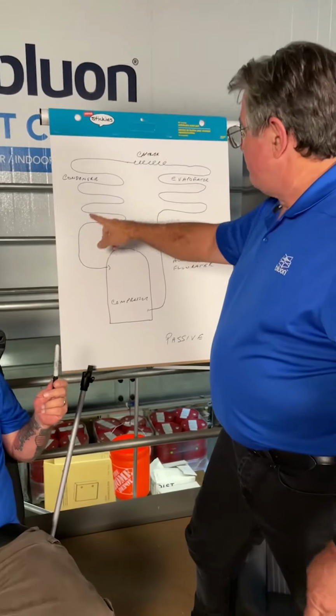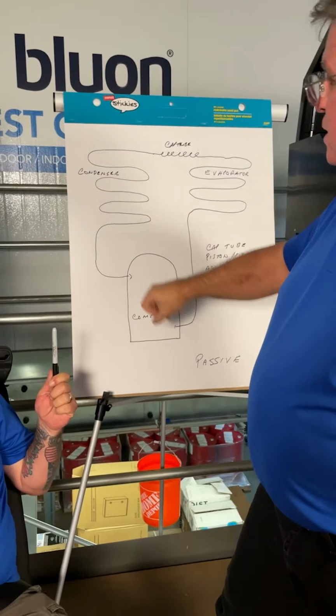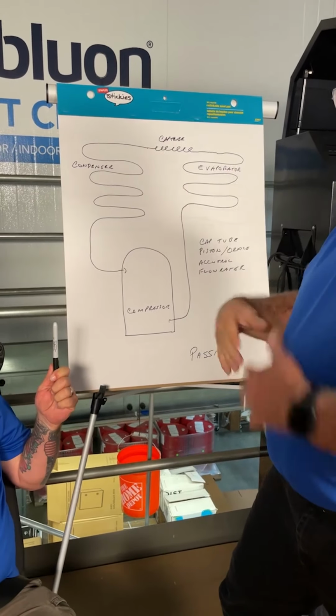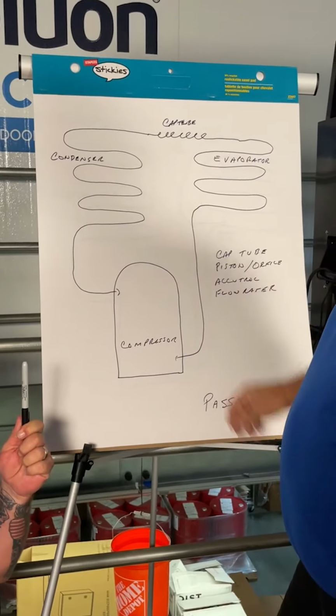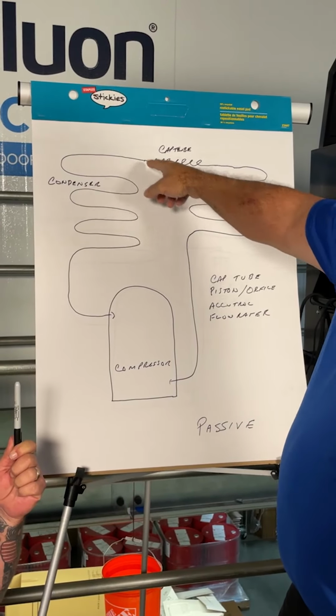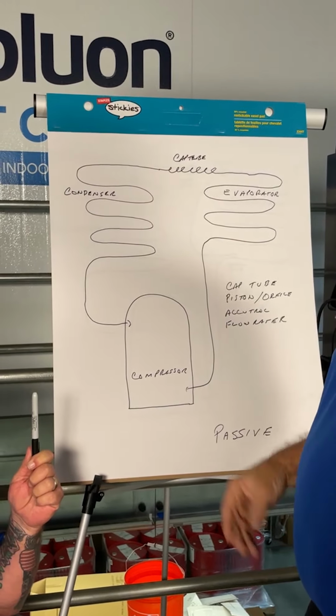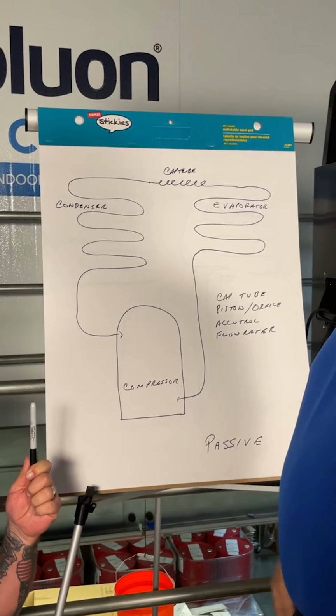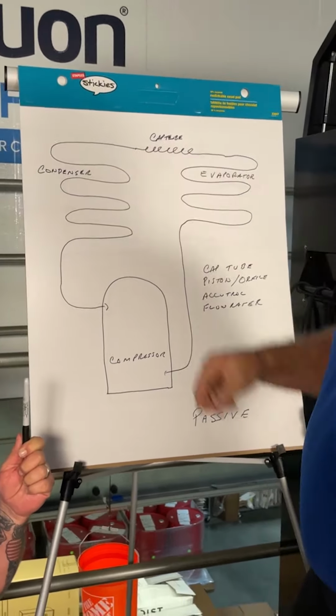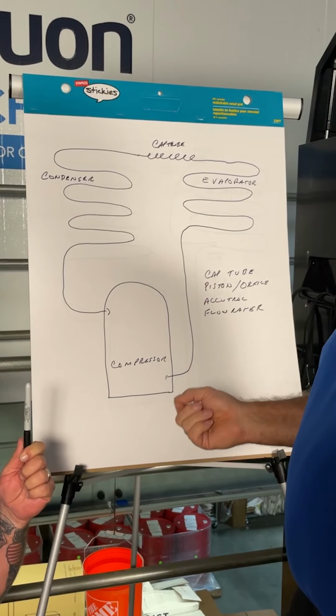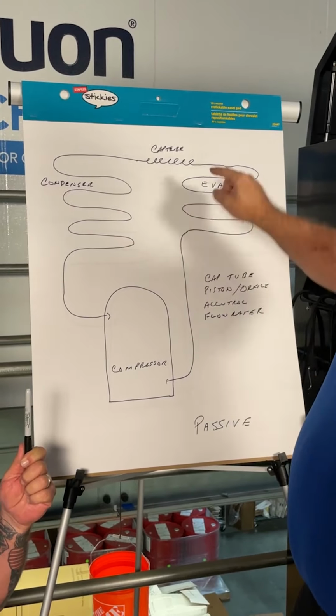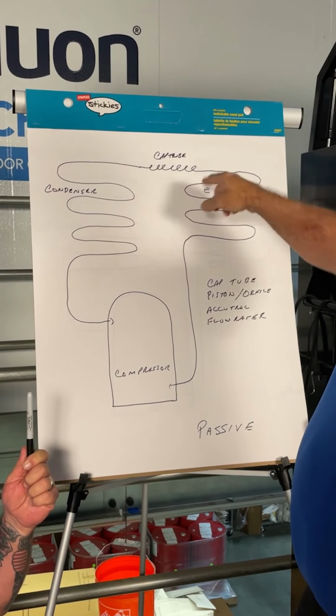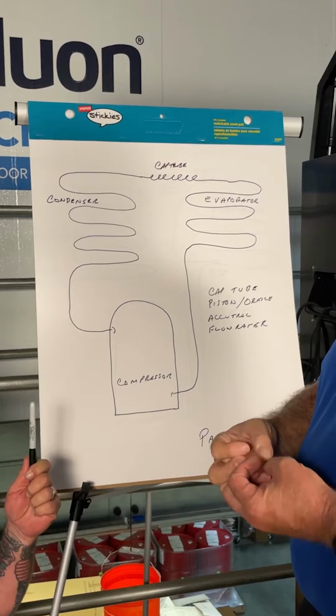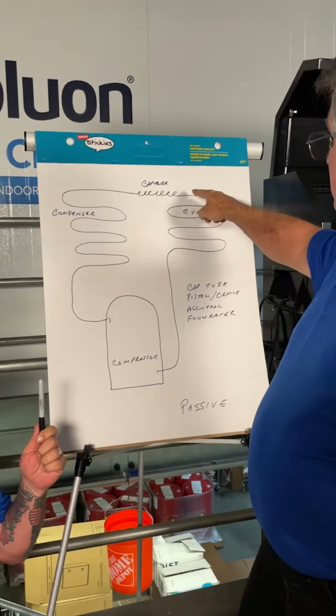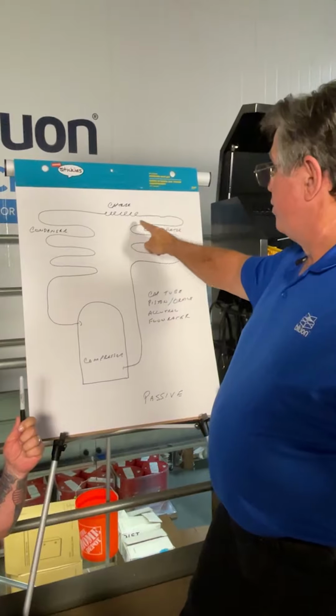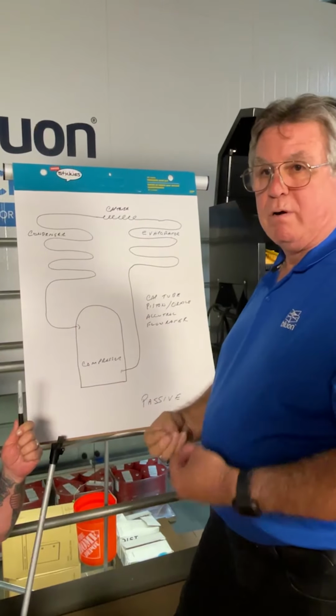So anyway, we leave the compressor here and we go into the condenser. Now, in most cases, you're going to have a fan blowing air across there, and that's going to help condense the refrigerant. And we're going to come up to the cap tube, and we're going to have a decent column of liquid there that is not saturated. It's subcooled. And the cap tube is a device to control the flow of refrigerant going into the evaporator. As it comes out of the cap tube, we're going to have our adiabatic expansion take place where we get that flashing off, and we're going to go in with a majority liquid. And as we go through the evaporator, we are going to absorb all that heat.